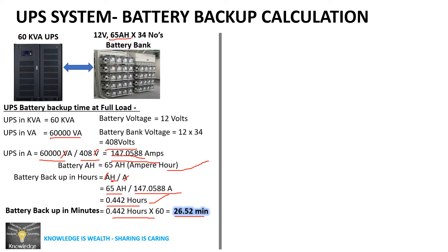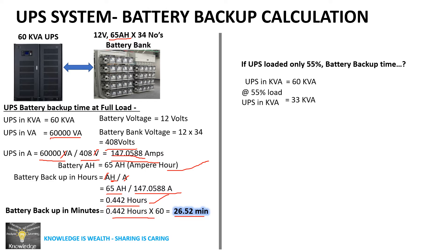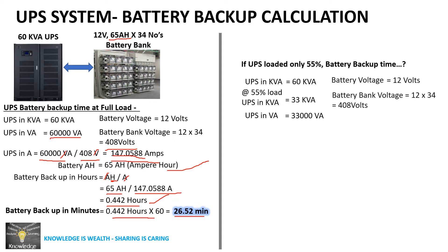So a 60 kVA UPS at full load, connected to a 65 Ah, 34-battery bank, will give around 27 minutes of backup. Now, what if this UPS is loaded at only 55 percent? The capacity is 60 kVA and 55 percent of that is 33 kVA, which is 33,000 volt-ampere. The battery bank voltage remains 12 × 34 = 408 volts.